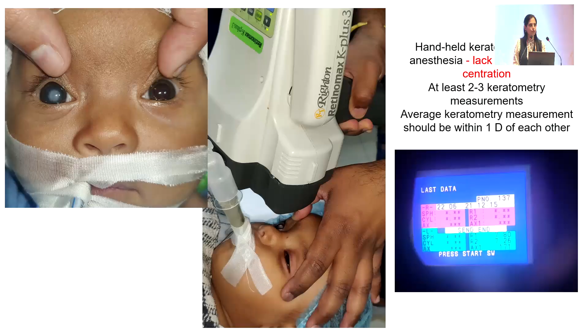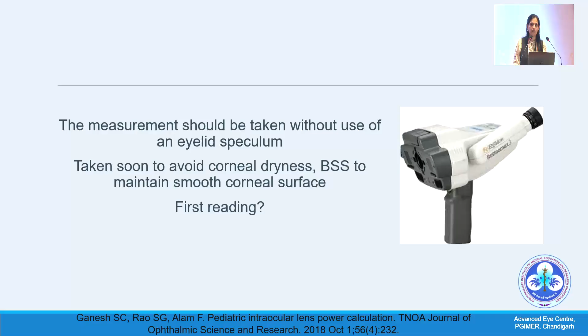Look at the standard deviation. It should not be very high, and all measurements should be within 1 diopter of each other. Most people like to take it as the first reading, even before you check the intraocular pressure, and take it without a speculum. Make sure the cornea is not dry to get an accurate reading.